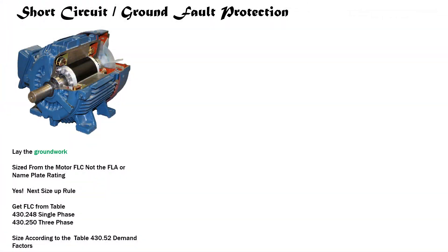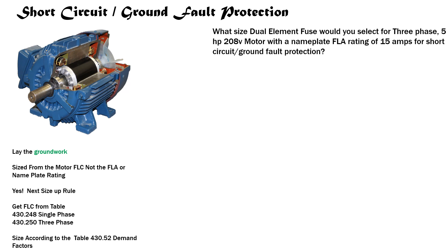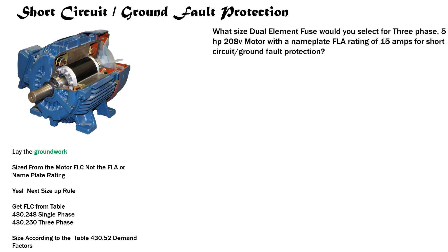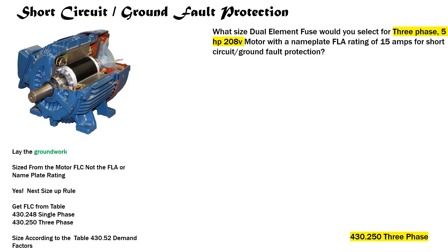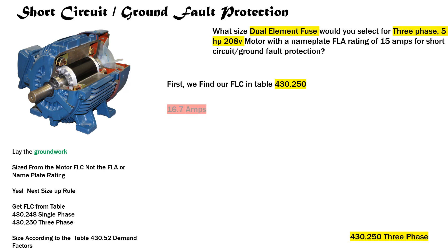This is how we become a master — repetition, repetition, repetition. Let's do it again. What size dual element fuse would you select for a three-phase, five horsepower, 208 volt motor with a nameplate FLA of 15 amps for short circuit and ground fault protection? It's three-phase, five horsepower, 208 volt, and a dual element fuse. We find our FLC in table 430.250 — it's 16.7 amps. Now we find our demand factor in table 430.52, which is 175 percent.